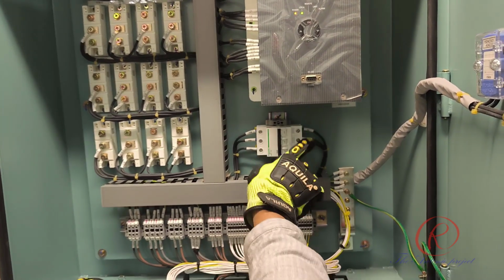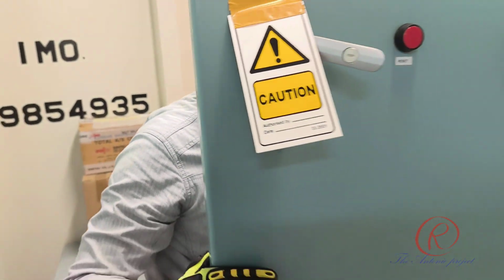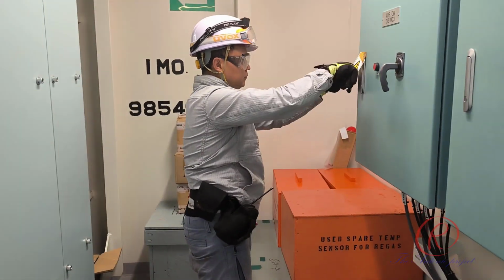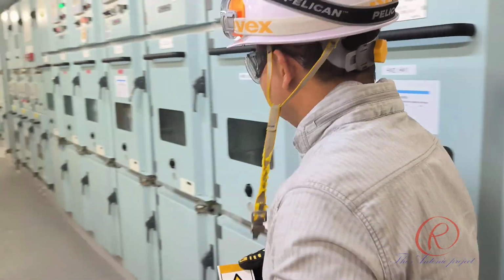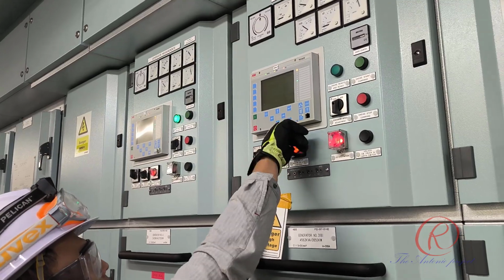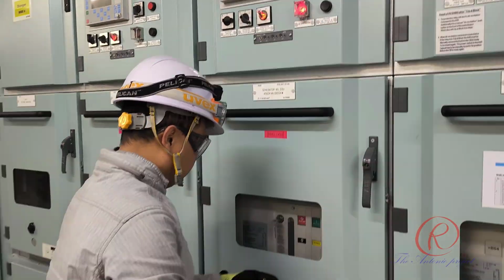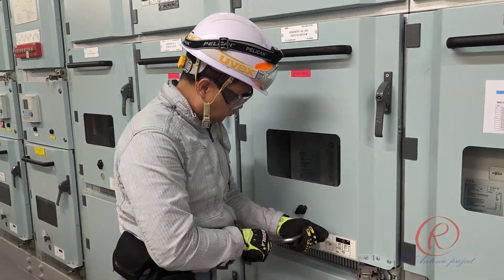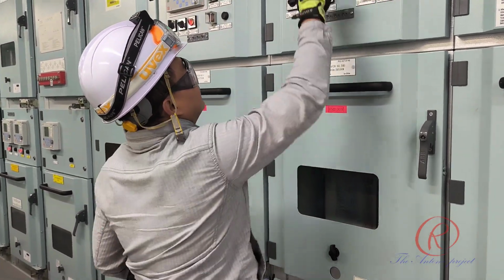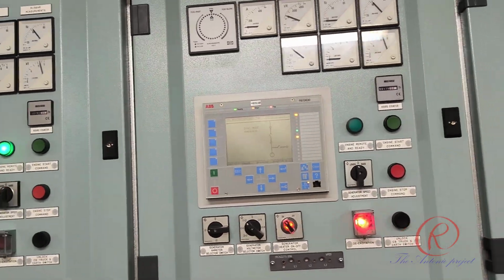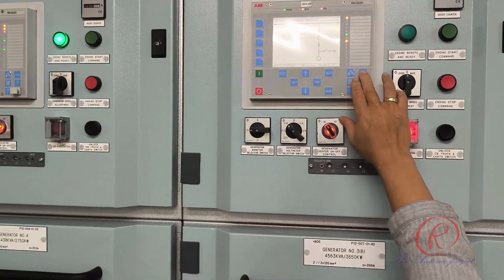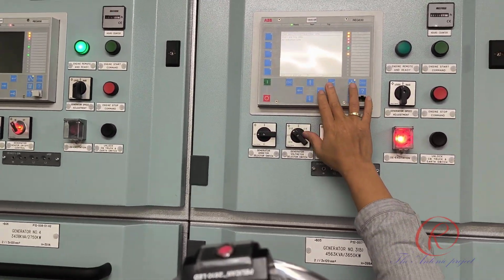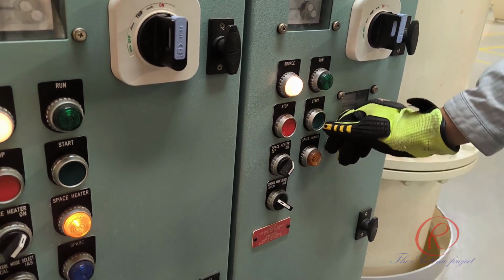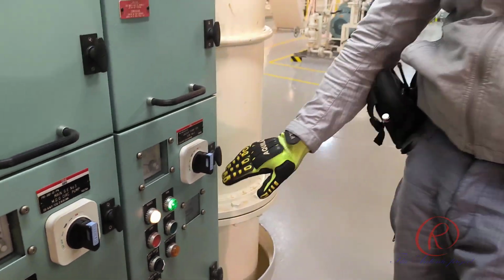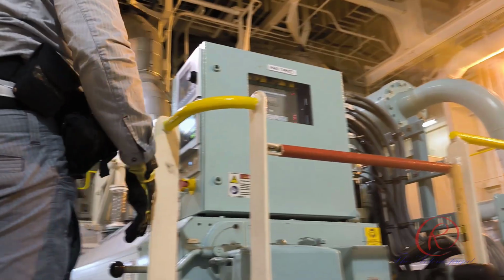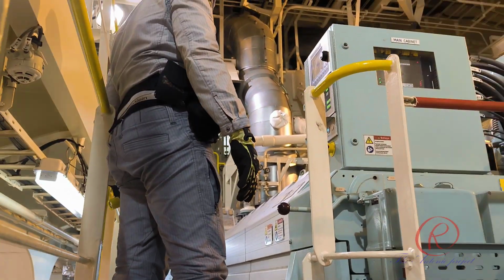Later on, AVR. Remove tape. Power on alternator capacitor. Rack in VCB breaker. VCB already racked in. Reset all alarms at the HMI monitor. Start jack up pump and set the control to auto. Set back main generator engine lever from stop to run.